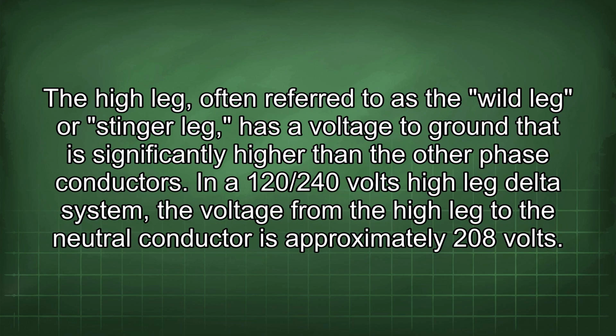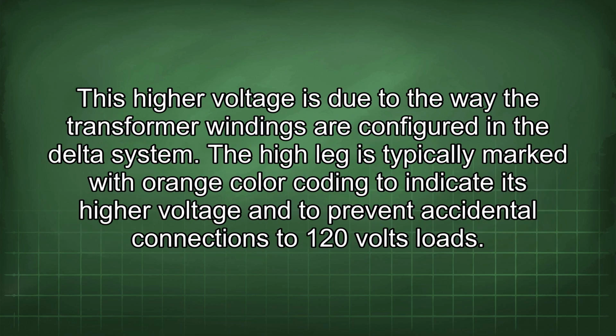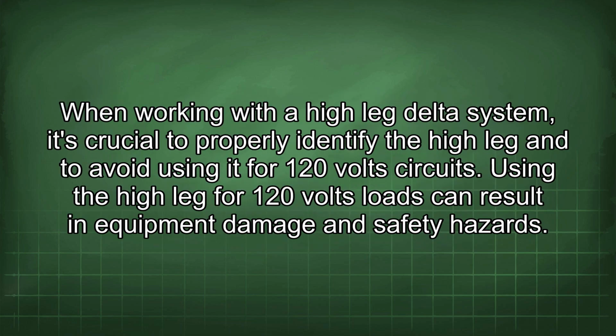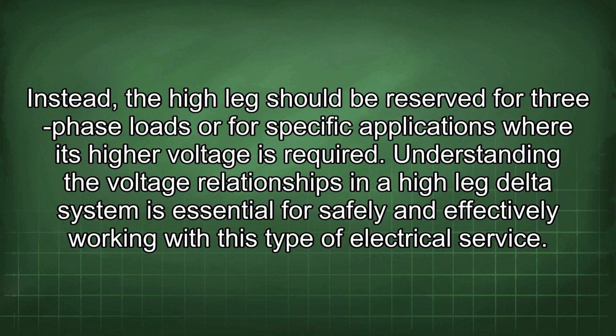The high leg, often referred to as the wild leg or stinger leg, has a voltage to ground that is significantly higher than the other phase conductors. In a 120/240 volts high leg delta system, the voltage from the high leg to the neutral conductor is approximately 208 volts. This higher voltage is due to the way the transformer windings are configured in the delta system. The high leg is typically marked with orange color coding to indicate its higher voltage and to prevent accidental connections to 120 volts loads. When working with the high leg delta system, it's crucial to properly identify the high leg and to avoid using it for 120 volt circuits. Using the high leg for 120 volts loads can result in equipment damage and safety hazards. Instead, a high leg should be reserved for three-phase loads or for specific applications where its higher voltage is required. Understanding the voltage relationships in a high leg delta system is essential for safely and effectively working with this type of electrical service.